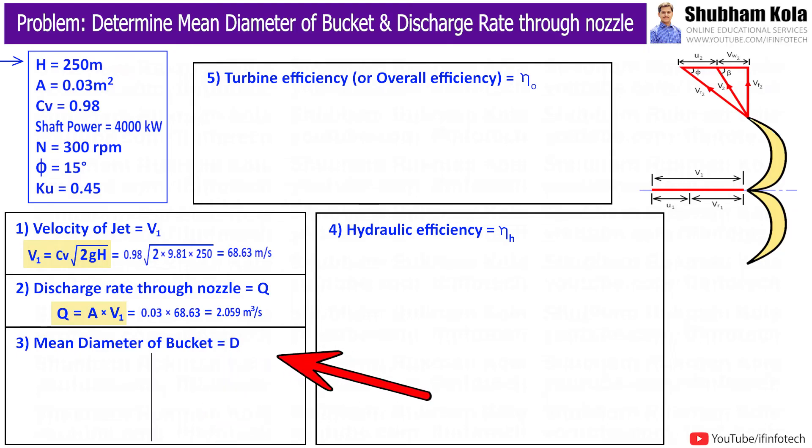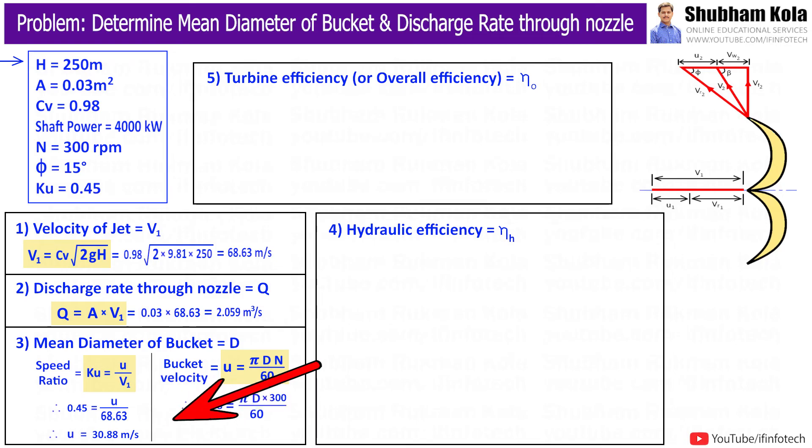Next we want to calculate mean diameter of bucket capital D. So, to calculate this value, we will use formula of bucket speed, small u, which is π DN by 60. And here we have speed capital N equal to 300 rpm. For the value of small u, we have speed ratio, i.e. bucket speed by velocity of jet is 0.45. So from here, we will get bucket speed small u. Therefore, to calculate mean diameter of bucket capital D, I will substitute calculated values of small u and speed N. So this will give me the value of mean diameter of bucket capital D as 1.966 m.